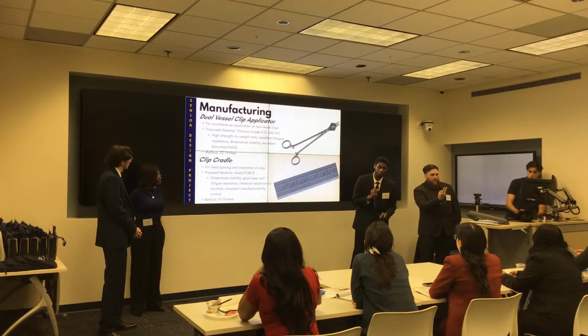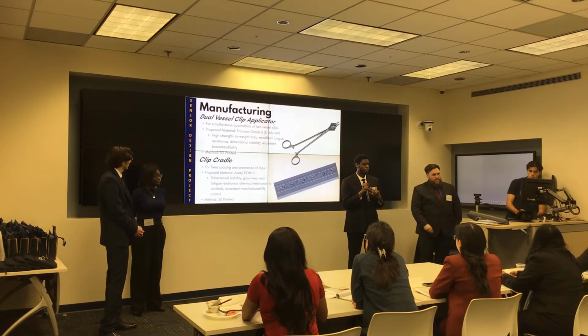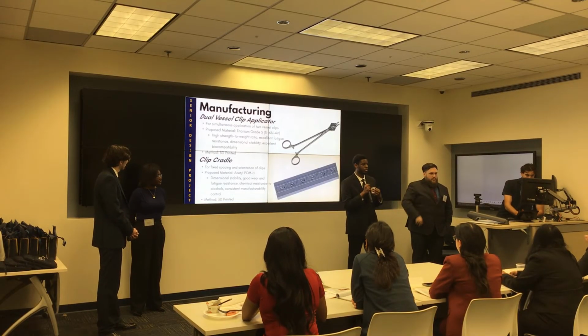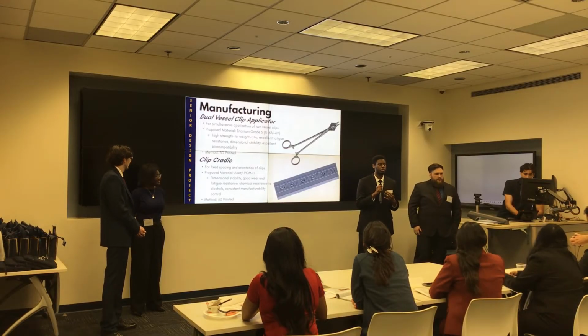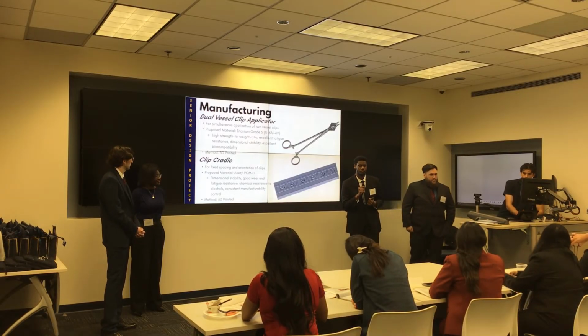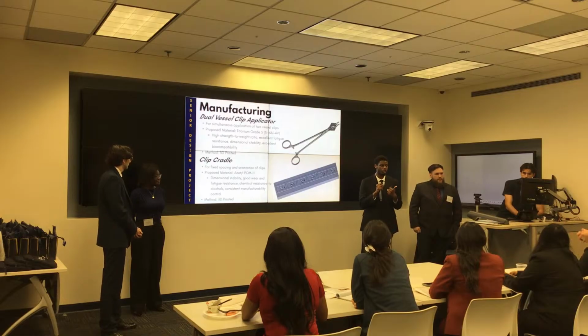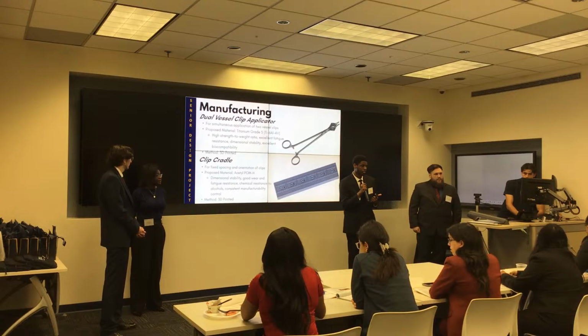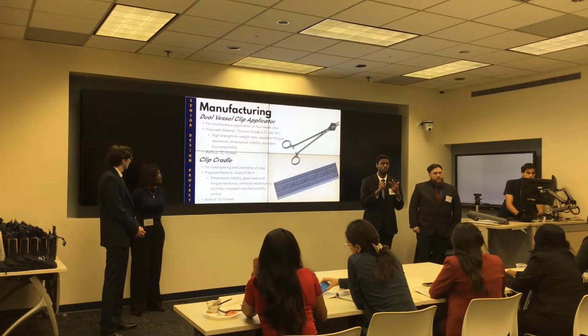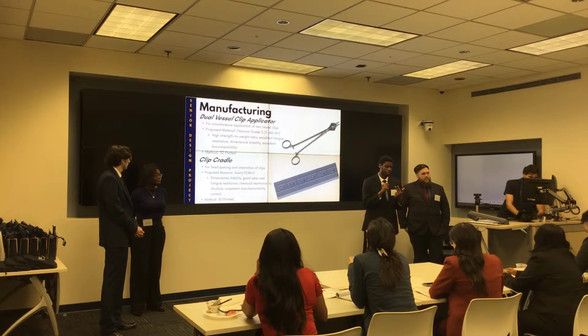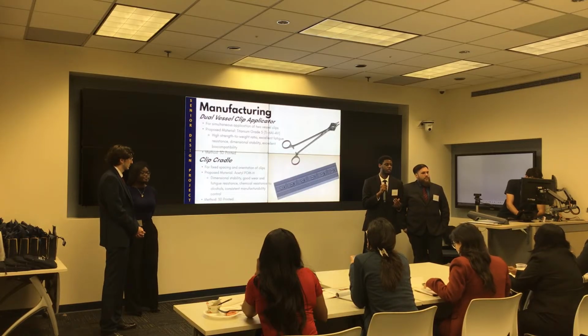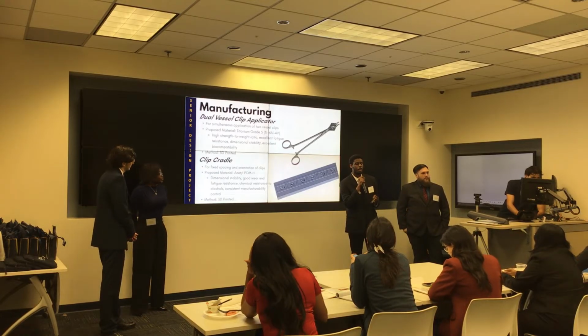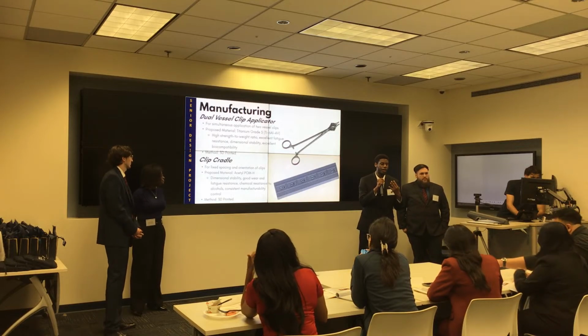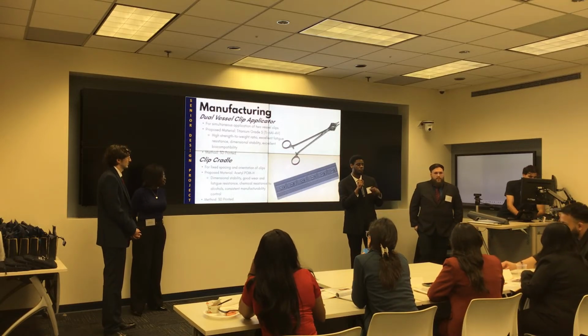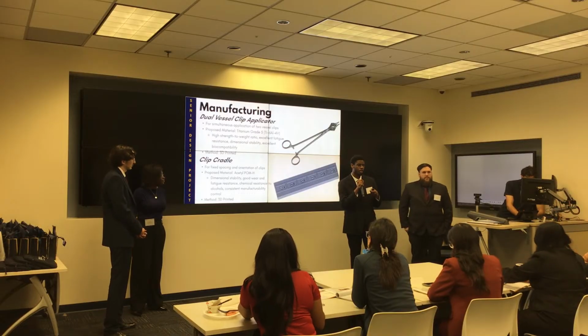And as for manufacturing, since our dual vessel clip applicator would be in contact with bodily fluid and tissues, we decided to go with the titanium grade 5 material for this device. This is because of its excellent biocompatibility, its excellent wear resistance, its low ion release to prevent the ion release into the body, as well as its high strength to weight ratio, allowing our device to be a very lightweight, however, reliably strong device in order to properly apply the forces needed to actuate the vessel clips.